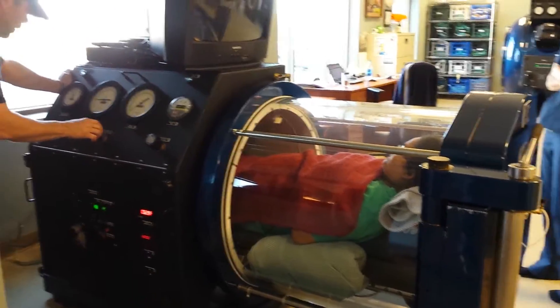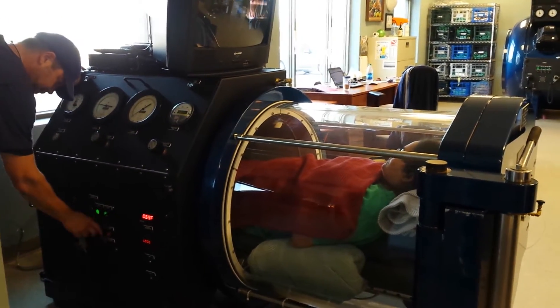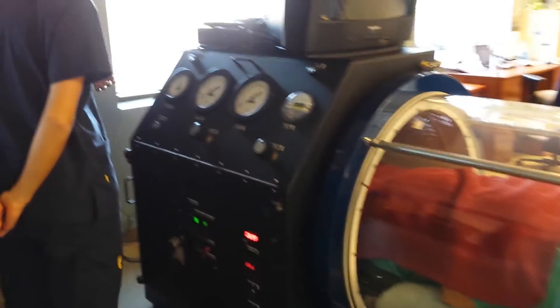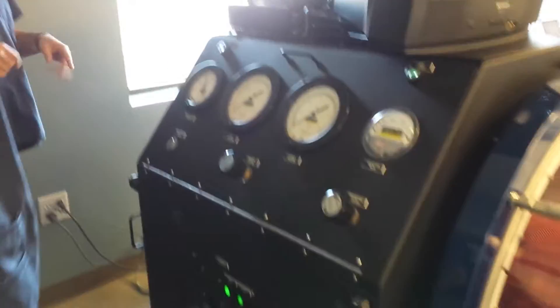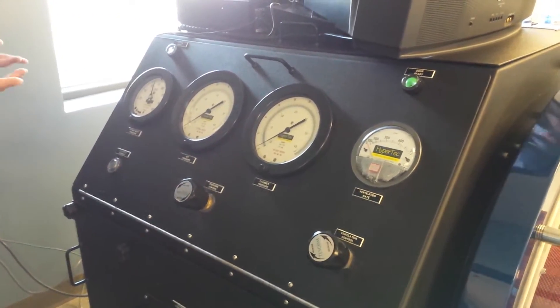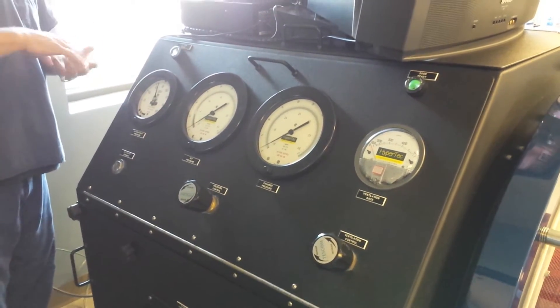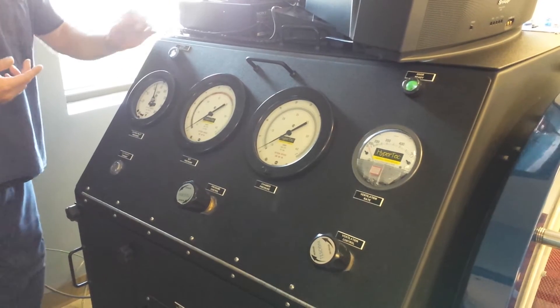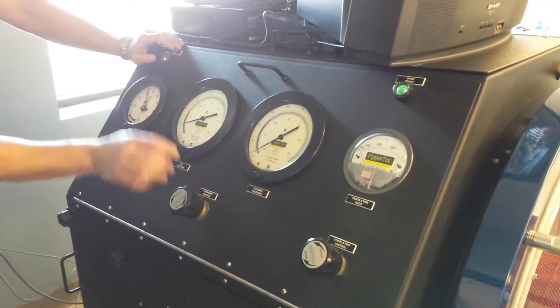It has to be a low wattage or low voltage type of speaker. You can come back here on the tube. I just dialed in this one here. Most of the newer ones, it's all computerized — they type in the ascent rate, they type in the descent rate, when it happens, when it doesn't. This one we're a little more manual. You dial it in. This one here is your set pressure — she's going to go to 1.5.